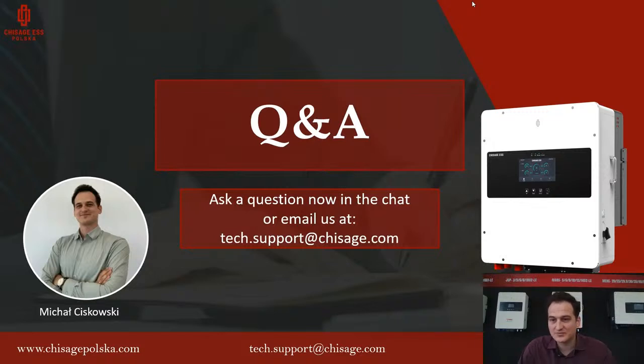Temp-co enable. What does it mean? That's the temperature coefficient. That's for lead acid batteries. So the coefficient index for temperature and voltage. Basically, you don't have to change this if you don't know what this means. It's set to -3 millivolts per degree, and that's okay as the default.